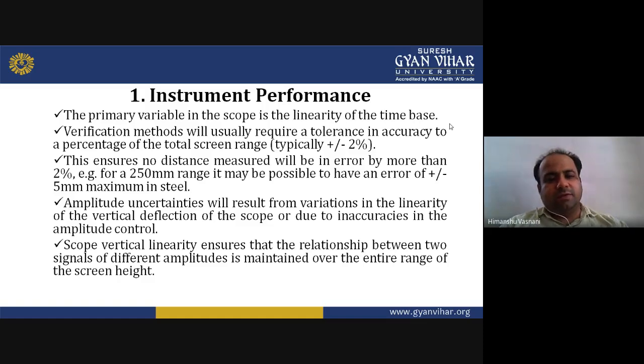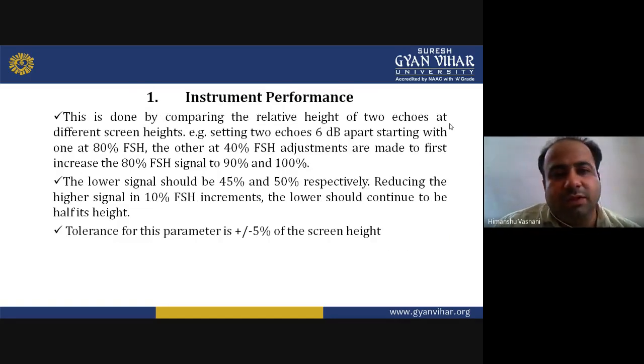Now amplitude uncertainty results from variations in the linearity of the vertical deflection of the scope, or due to inaccuracies in the amplitude control. The scope vertical linearity ensures that the relationship between two signals of different amplitudes is maintained over the entire range of the screen height. This is done by comparing the relative height of two echoes at different screen heights. Example, getting two echoes 6 decibels apart, starting with the first at 80% FSH and the other at 40% FSH, adjustments are made to the first to increase the 80% FSH signal to 90 and 100%.